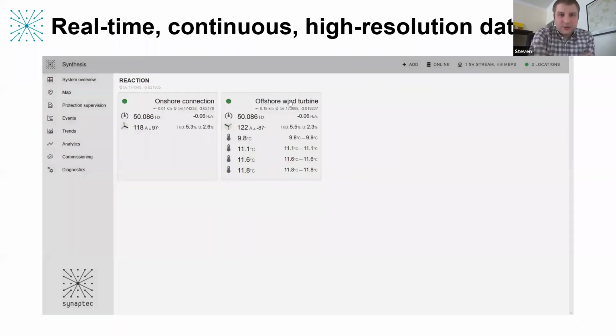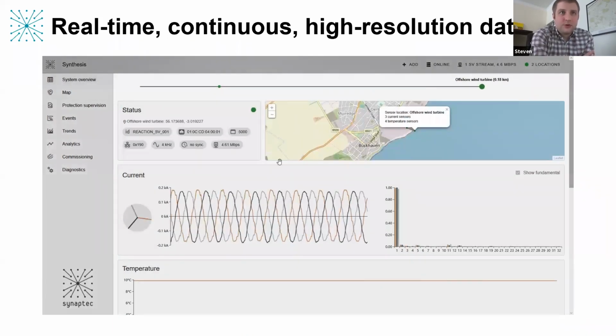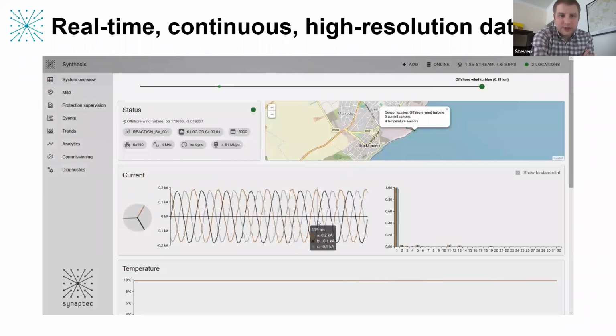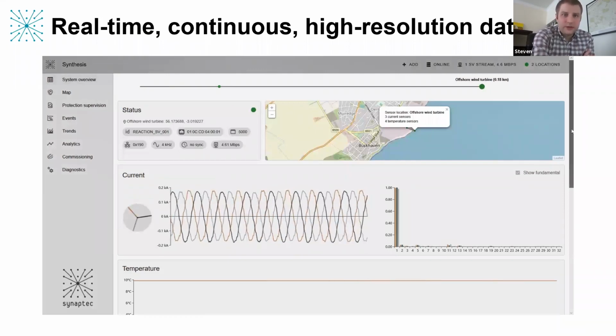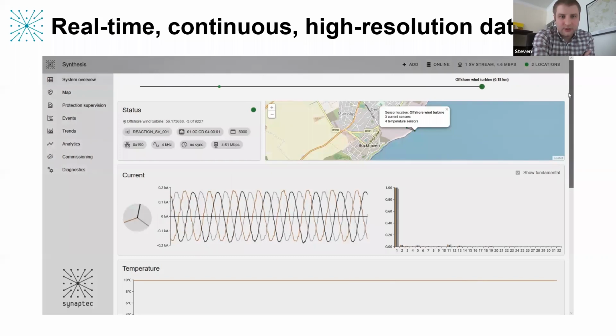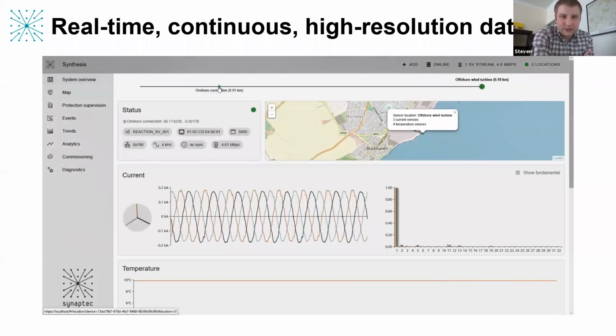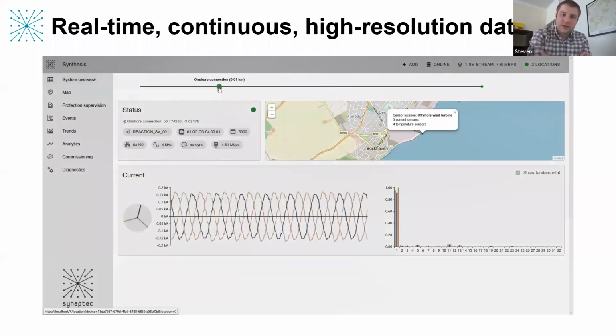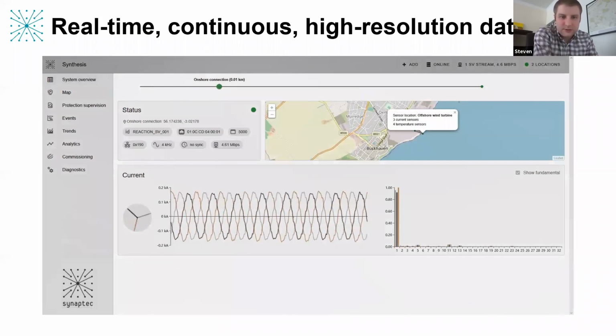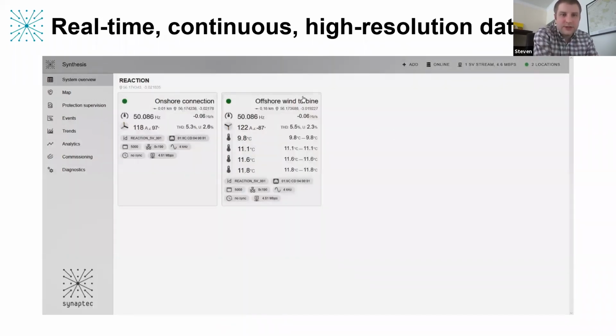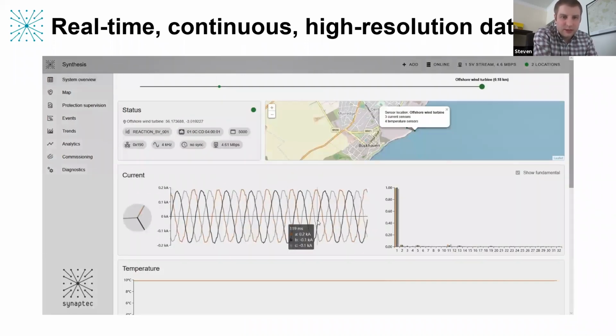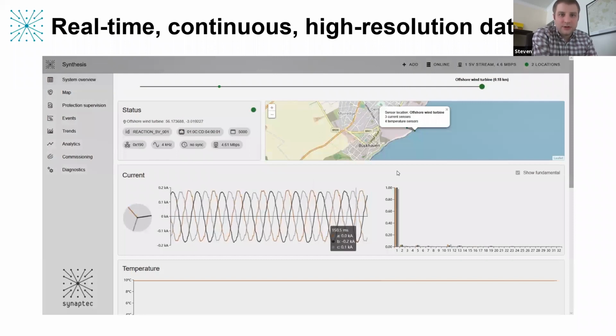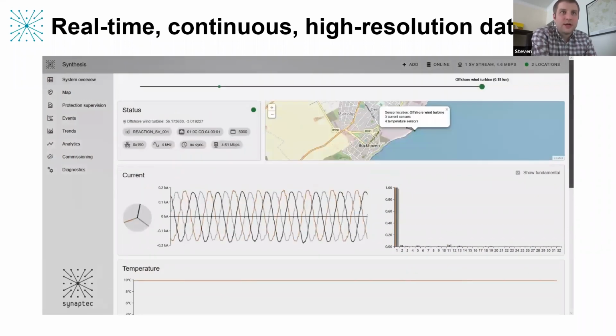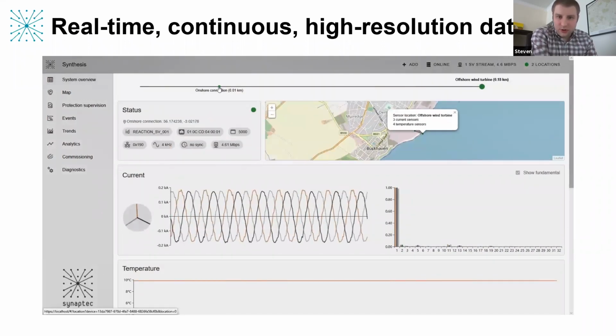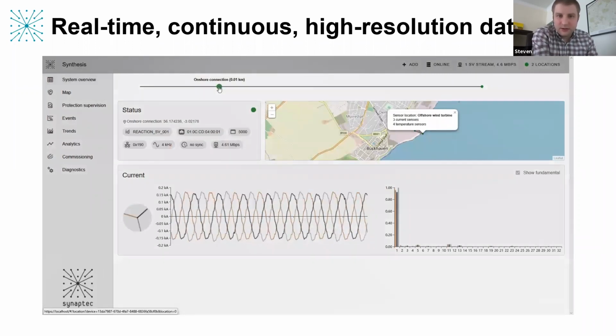This next screen expands on that, and it shows you a more detailed view for each individual location. Here you have access to the full detail of the measurement waveform down to the individual samples. In this case, we're sampling at 4 kilohertz, so we've got that really detailed view. It's seamlessly built into this visualization, which is unusual to have access to, especially in real time. It's also automatically performing some power quality measurements.